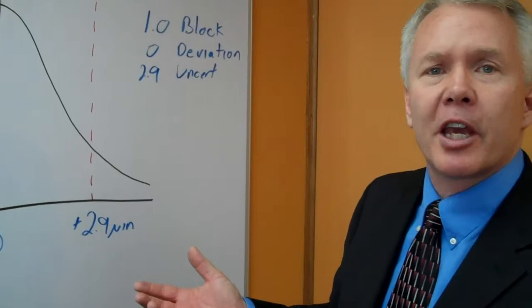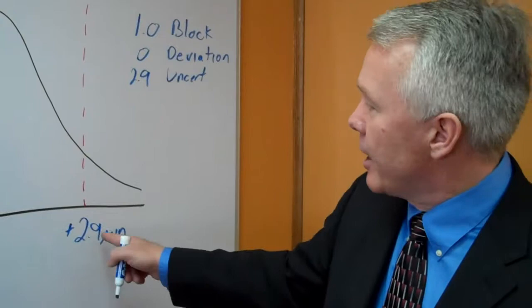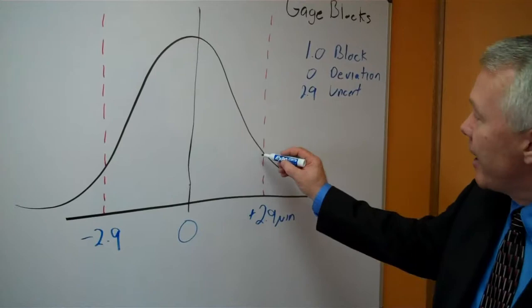What that means when we tell you that a one-inch gauge block is exactly one inch, if you look at the standard deviation of 2.9 with a k equal 2 factor, which is referred to in the industry pretty commonly, it could be minus 2.9 millionths, it could be plus 2.9 millionths.